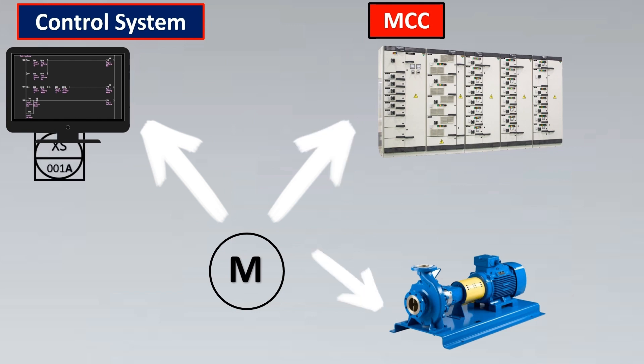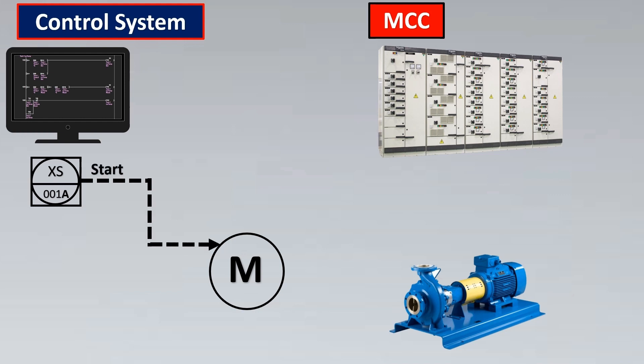Let's have a switch on the control system called XS. This switch is for an operator to turn on the motor. This hardwired signal is called a start switch. In the actual world of wiring, the start signal will go to the MCC, from the MCC it will go to the motor or the pump, and it will start the motor.